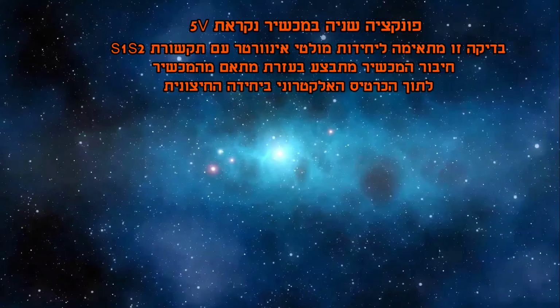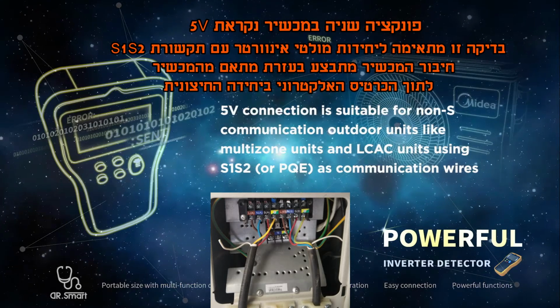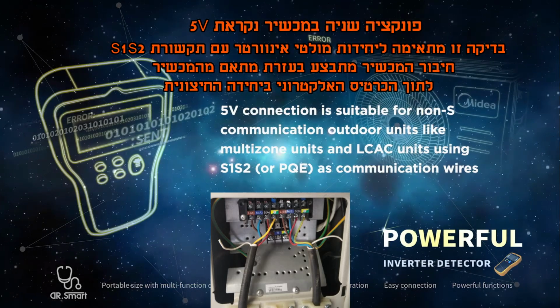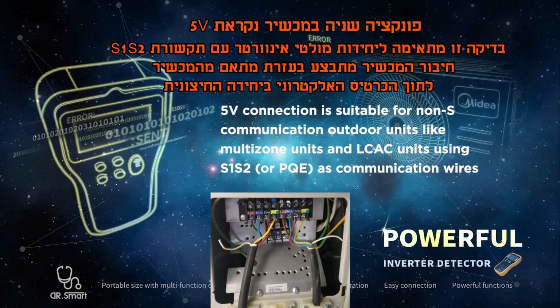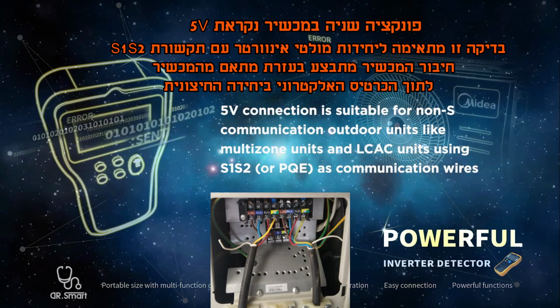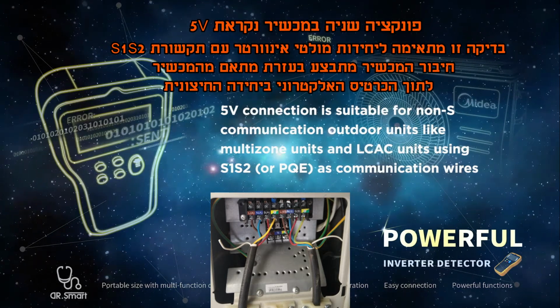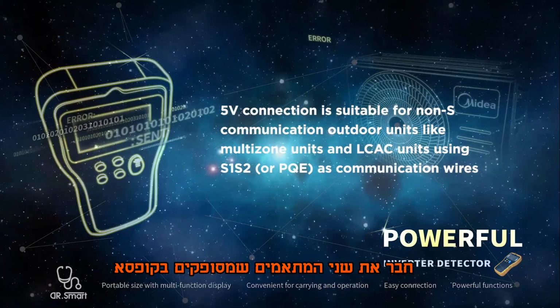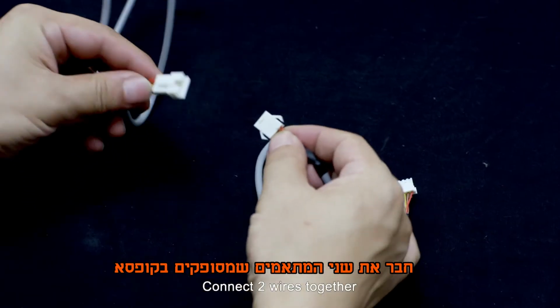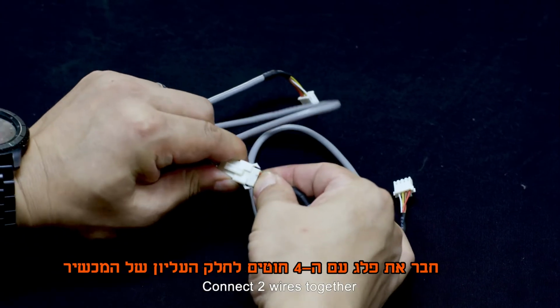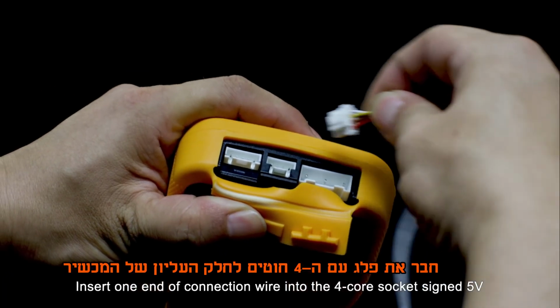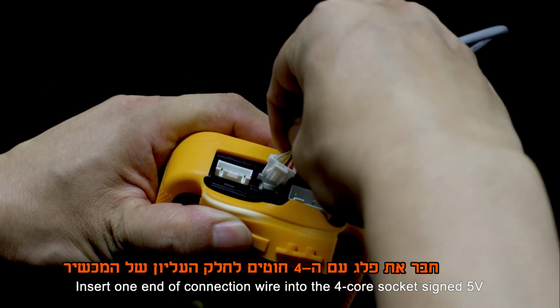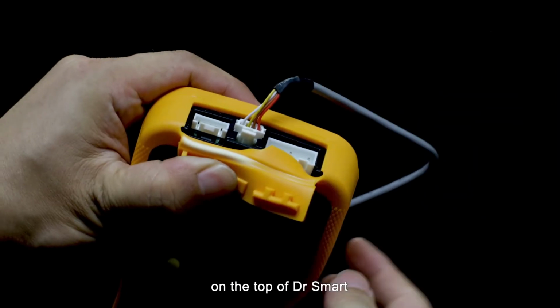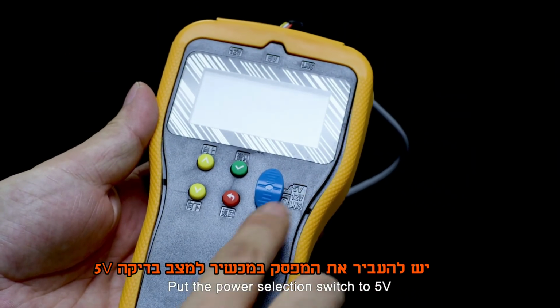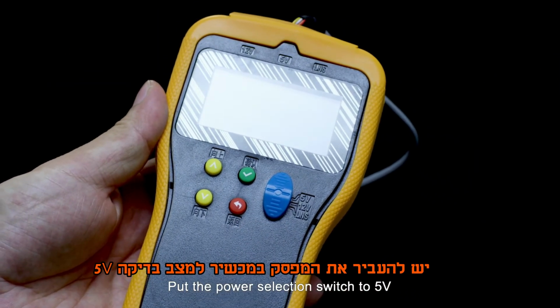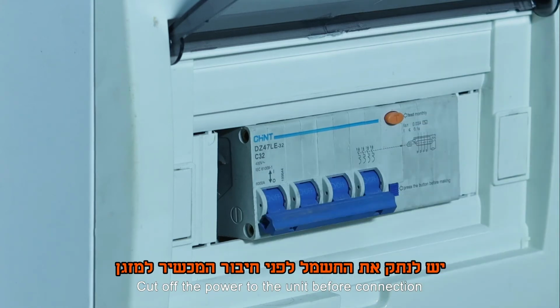5-volt connection. 5-volt connection is suitable for non-S communication outdoor units like multi-zone units and light commercial units using S1S2 or PQE as communication wires. Connect 2 wires together. Insert one end of connection wire into the 4-core socket signed 5-volt on the top of Dr. Smart. Put the power selection switch to 5-volt. Cut off the power to the unit before connection.